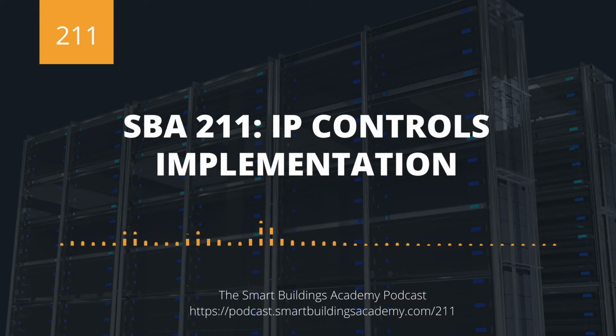So you run into this scenario where you want to put in your IP controls, you want to get them all commissioned and communicating, but you have no switches to communicate with, no switches to connect to. And so we're seeing where you're either having to have some unmanaged switches, or you're having to have some industrial switches that you put in place to get the network up and working, and then you have to go and actually switch the IP controls over to the new networking gear once IT puts it in place.